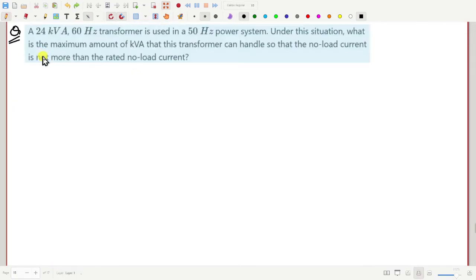Now let's take an example. Suppose we have a 24 kVA 60 Hertz transformer which is used in a 50 Hertz power system. Under this situation, what is the maximum amount of kVA that this transformer can handle without increasing no load current?